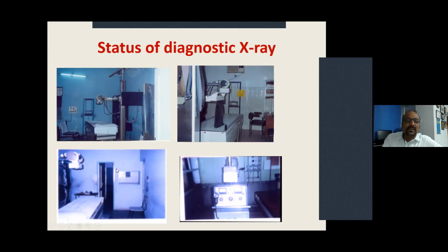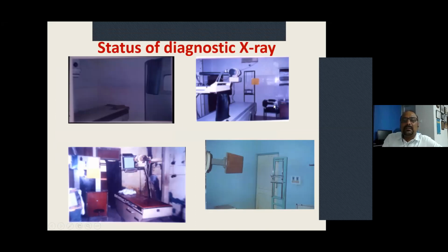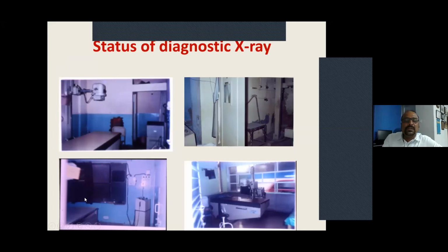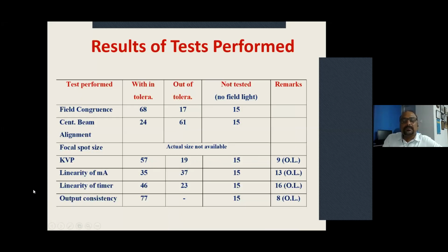Windows are there. This door you can see in front of the X-ray machine. Similarly, here also this chest stand is near the door, and a person is sitting inside. Similarly, over here these windows are there, so anybody outside the window will be getting the radiation. For an X-ray department, a minimum 9-inch wall thickness is required for the shielding. And this is the result of the machine.